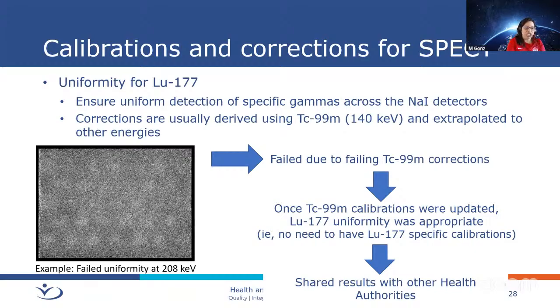What this taught us was that as long as the cameras are properly calibrated with technetium, we can use that for lutetium. This was a big time saver, because it means we don't have to calibrate each camera specifically for lutetium. As long as technetium calibrations are okay, you can use that for lutetium. Again, we shared those kinds of results with all health authorities, so nobody had to reinvent the wheel. But that still meant that all 20 cameras had to be checked to make sure that their performance was okay.